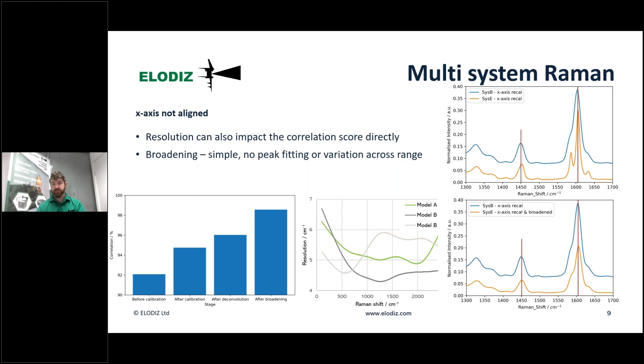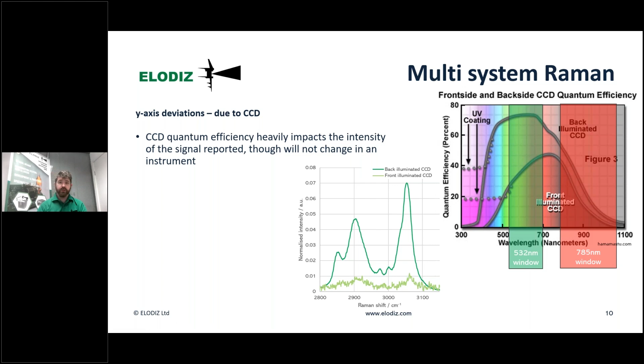The next thing I'm going to talk about is the y-axis deviation. Enrique was talking about the fact that there are many different reasons for it. One of those reasons is just the type of CCD technology, for example, that you have. Both of these spectra that you see in green are taken from 785 nanometer spectrometers. One of them has a much clearer, much more obvious peak structure in the CH band, whereas the light green, the front illuminated CCD, has a much weaker signal and a much weaker response in that region. That's partially because if you consider that region on the wavelength axis, that region is about here. So you're looking at the difference between these two quantum efficiencies, and that is a significant improvement when you're using back illuminated CCDs.